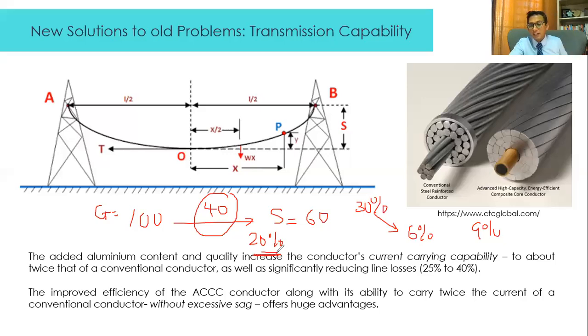How to bring that down, new technology can help. With the ACCC conductor, you can reduce line losses, improving efficiency and carrying twice the current without excessive sag. You could achieve the same with a bigger conductor, but the sagging would be much more, since it would be heavier. When it sags more, you have less clearance, which compromises safety, one of the key characteristics we mentioned.